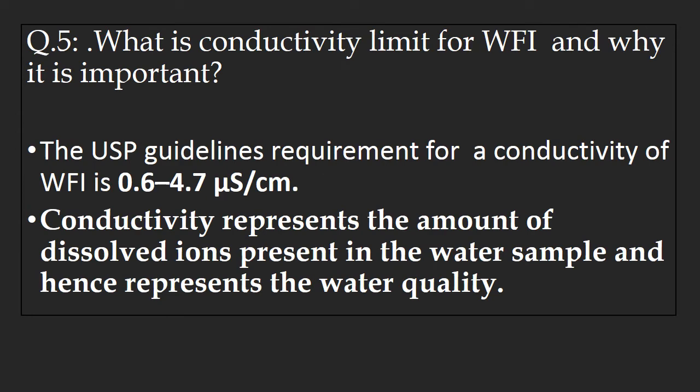Question number 5: What is the conductivity limit for WFI and why is it important? The USP guidelines requirement for conductivity of WFI is 0.6 to 4.7 microsiemens per centimeter. Conductivity represents the amount of dissolved ions present in the water sample and hence indirectly represents water quality, which is why conductivity testing is important for WFI.